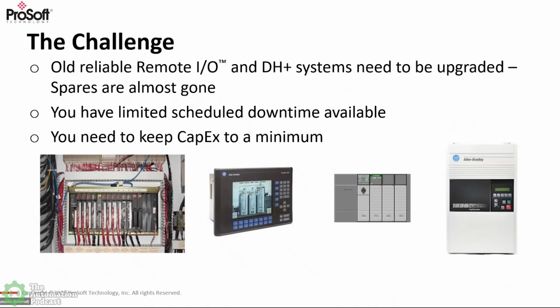And this is not just your old racks of I/O. This is for really anything that's sitting on remote I/O. It could be a VFD, an old panel view—one of those original panel views, or panel view 1200s, 1400Es, even a standard panel view or panel view plus, although I wouldn't do a panel view plus, or old SLC 500s. So it's not just 1771 I/O—because of the way remote I/O works, it's really anything sitting on the remote I/O side, and anything talking Data Highway Plus on the Data Highway Plus side.